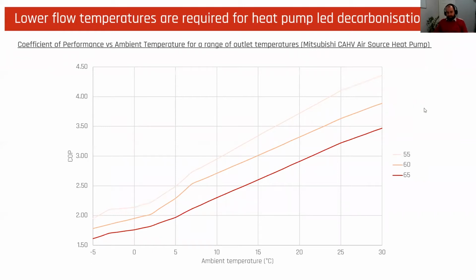However, we can't just fit heat pumps into legacy buildings. Legacy buildings tend to have higher operating temperatures, whether they have hot water cylinders or radiators, the fabric efficiency isn't so good, so they need to operate at higher temperatures. But unfortunately, the efficiency of a heat pump is governed by the temperature that you produce heat out of that heat pump.